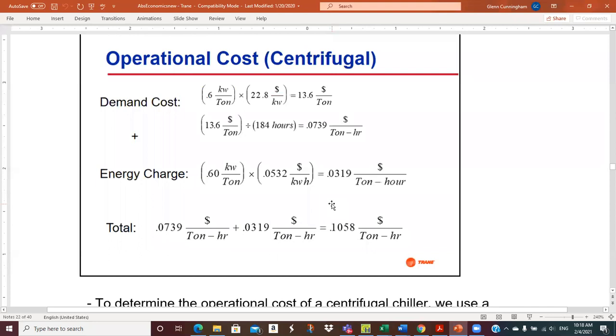Cost for centrifugal. And so here we have demand and energy. It's kind of interesting to see what he does on the demand. It's kind of like the COP on the machine. It's not really a COP because it's got units, but it's the efficiency of the unit, I guess you'd say. So it requires 0.6 kW of power per ton of refrigeration. And notice that's a rate over a rate, because kW is kilonewton meters per second, and ton is BTUs per hour. We've got all kinds of units floating around, but it's a rate over a rate.